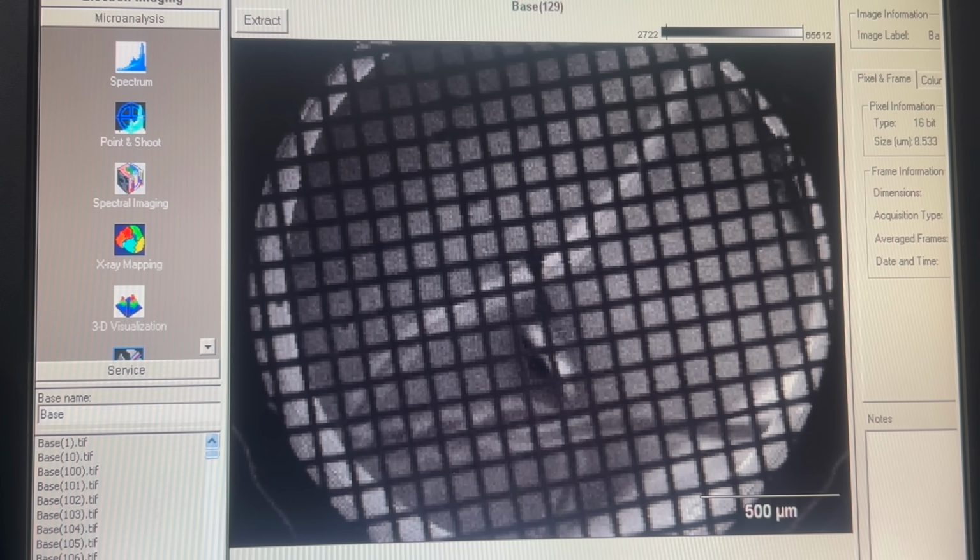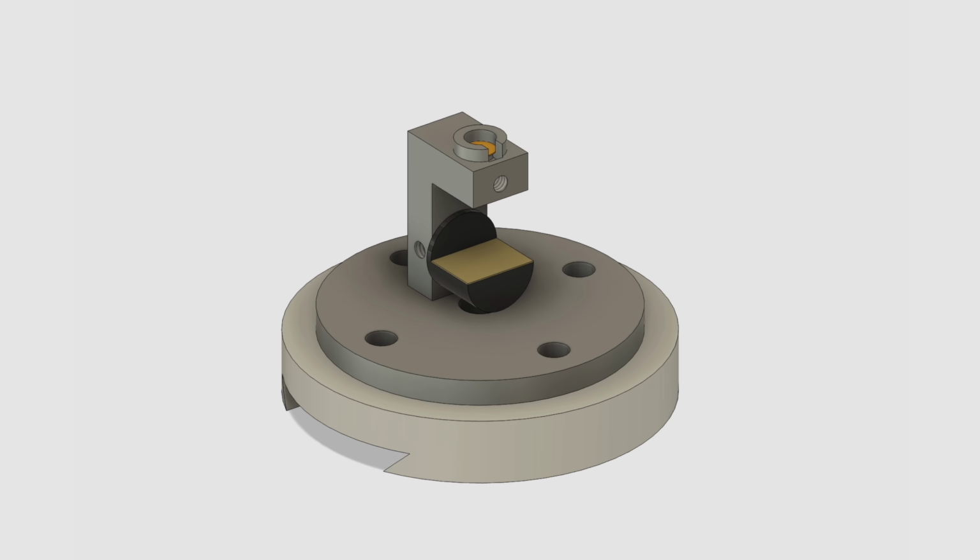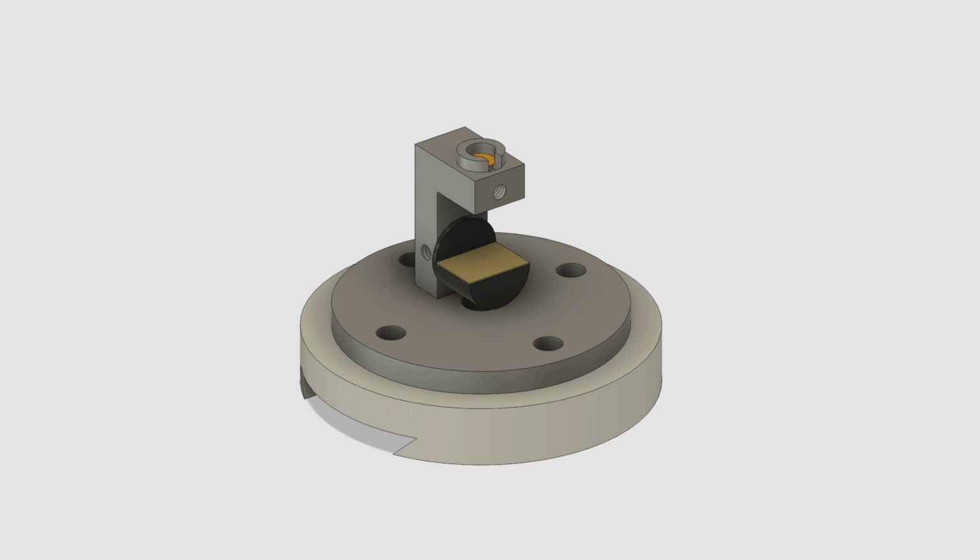I set up the computer capture device and took a set of photos in order to measure this effect. It's clear that if we want to maximize the contrast, then we should obviously tilt the mirror as much as we can. However, there is an obvious problem. If we tilt the mirror too much, then only the samples in the very center of our image are going to have the mirror still underneath. The exact location of the sample on the grid will limit the maximum tilt of the mirror. That is an inevitable limitation of this type of STEM-in-SEM adapter.